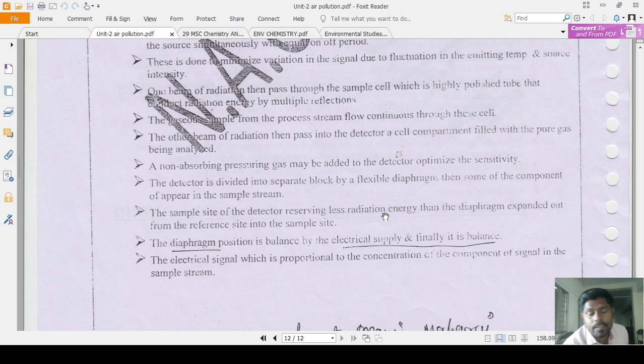Because of that reason, the level of the diaphragm is changed. That means when the sample is entered, the beam from the sample is entered, and the diaphragm is displaced from the original position. When the pure gas is entered, the beam is entered from the pure gas. So that position of the diaphragm is balanced with the help of electrical supply.